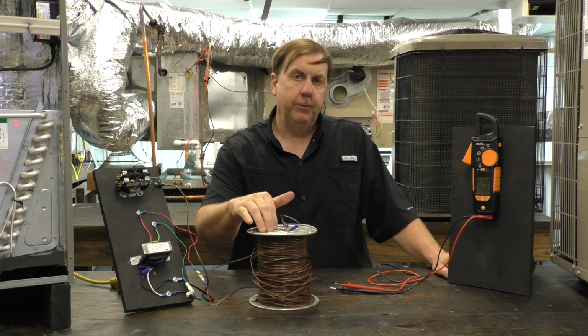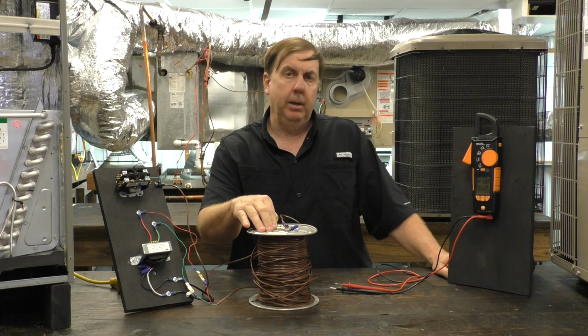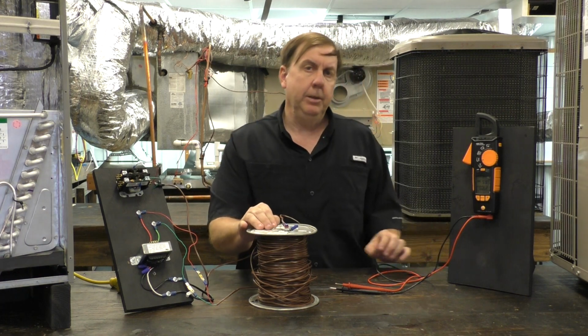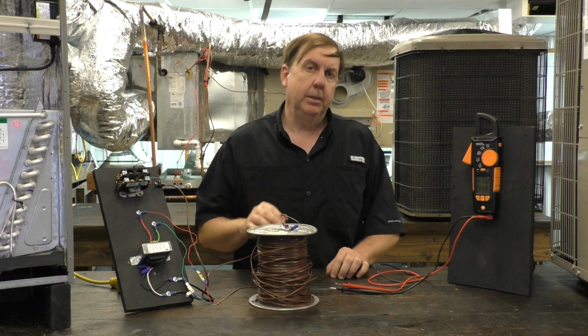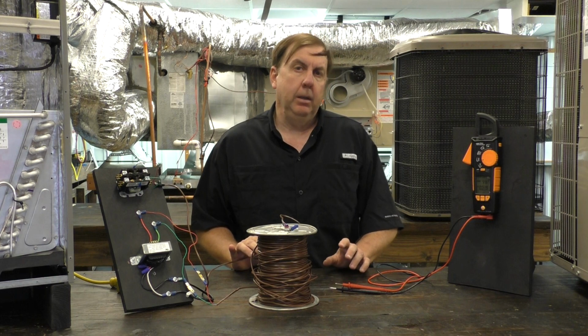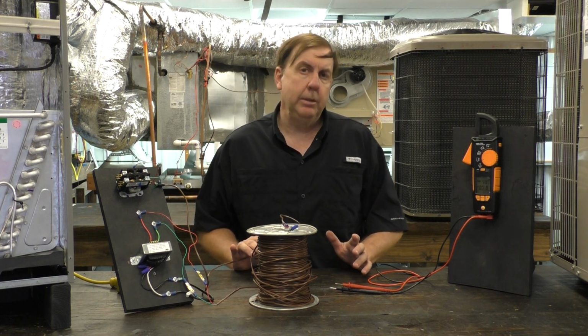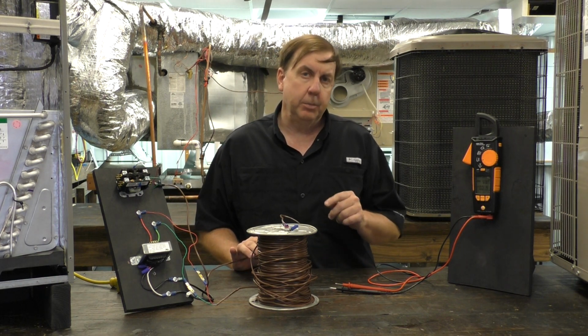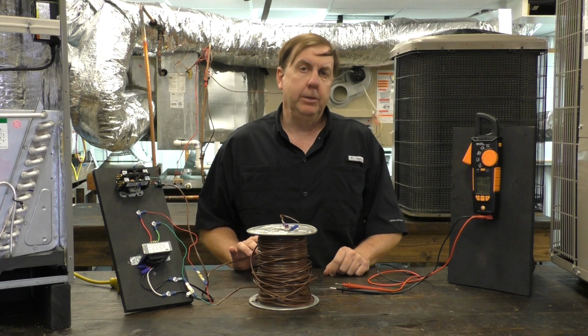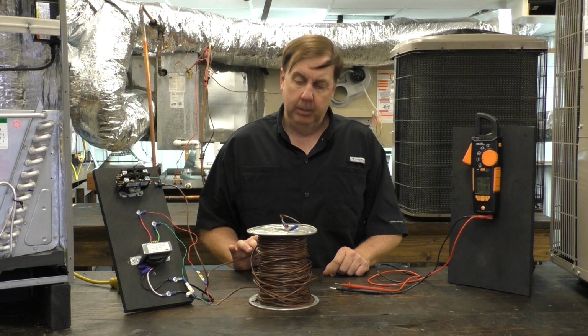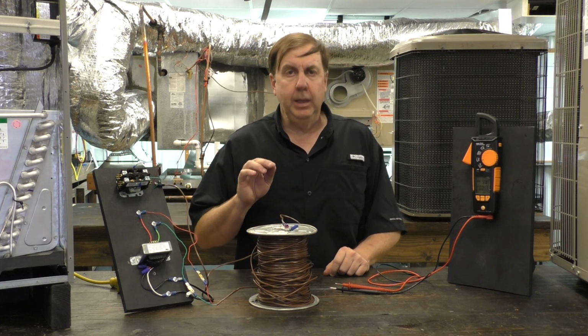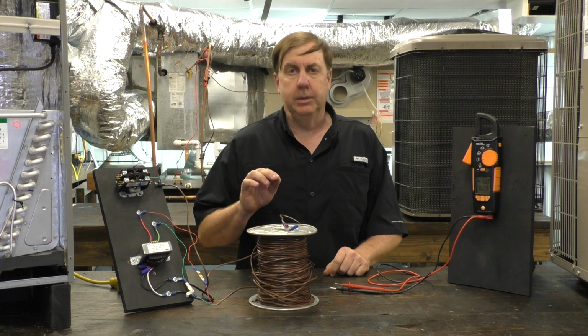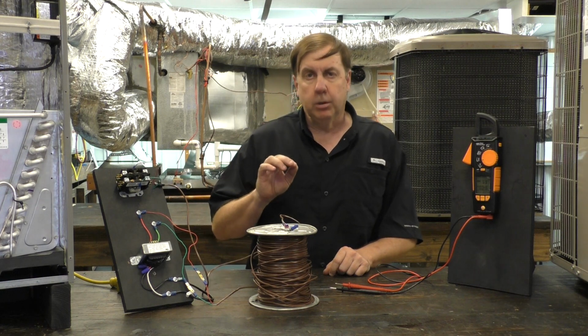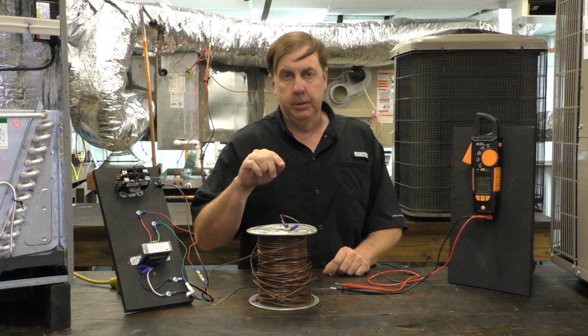Now this wire in front of me, this 500-foot spool of wire, is 18 gauge wire. That's pretty big in terms of thermostat wire. A lot of homes have 24 gauge wire, and the bigger the gauge number, the smaller the wire. 24 gauge wire is a lot smaller and the voltage drop is a lot more prevalent. So what I'm going to show you is that even the 18 gauge wire can give us at least a 1 volt drop when we hook it up to this transformer.